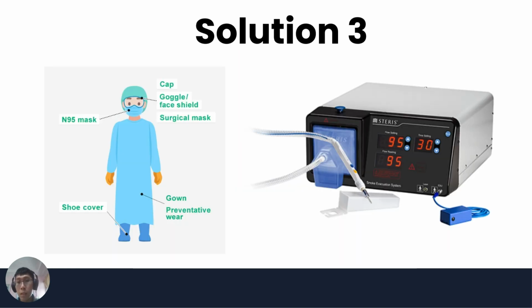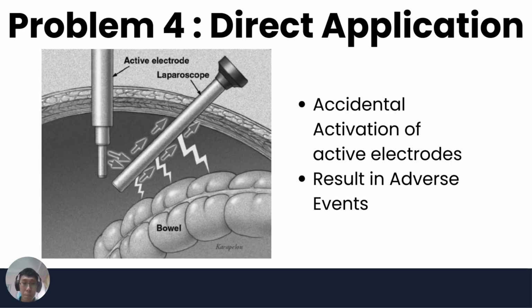The solution to smoke is to decrease the risk to both patients and staff. Hospitals should equip their operating rooms with a smoke evacuation system, limiting the smoke plume before it can travel any further distance in the operating room. In addition, the surgeon should always wear suitable personal protective equipment. When a smoke plume is emitted into the operating room, local exhaust ventilation is recommended. It has different types of designs and purposes, such as portable smoke evacuators and room suction systems. None are without some hindrance to the ease of use by the surgeons. The irritancy of surgical smoke may disturb some staff harmfully despite effective LEV.